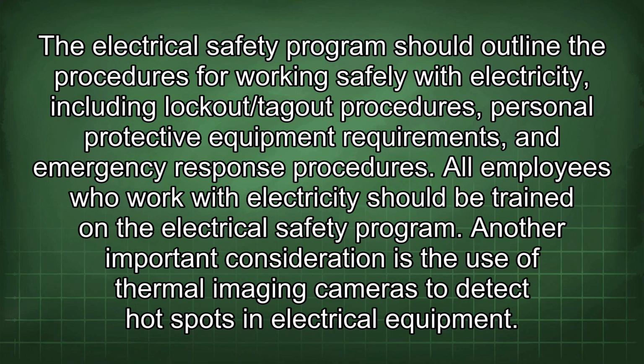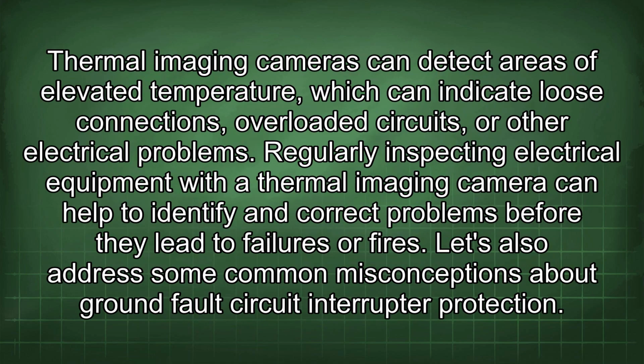Another important consideration is the use of thermal imaging cameras to detect hot spots in electrical equipment. Thermal imaging cameras can detect areas of elevated temperature, which can indicate loose connections, overloaded circuits, or other electrical problems. Regularly inspecting electrical equipment with a thermal imaging camera can help to identify and correct problems before they lead to failures or fires. Let's also address some common misconceptions about ground fault circuit interrupter protection.